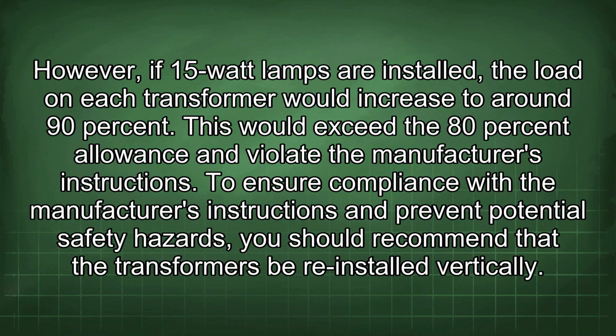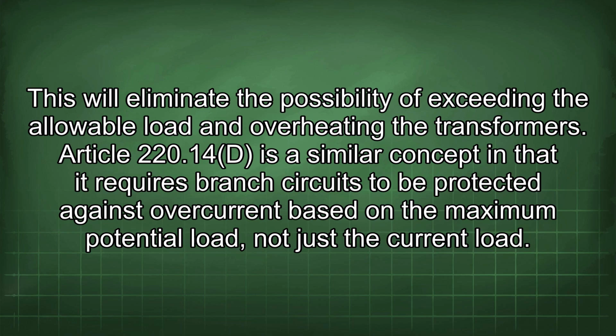However, if 15-watt lamps are installed, the load on each transformer would increase to around 90%. This would exceed the 80% allowance and violate the manufacturer's instructions. To ensure compliance with the manufacturer's instructions and prevent potential safety hazards, you should recommend that the transformers be reinstalled vertically. This will eliminate the possibility of exceeding the allowable load and overheating the transformers.